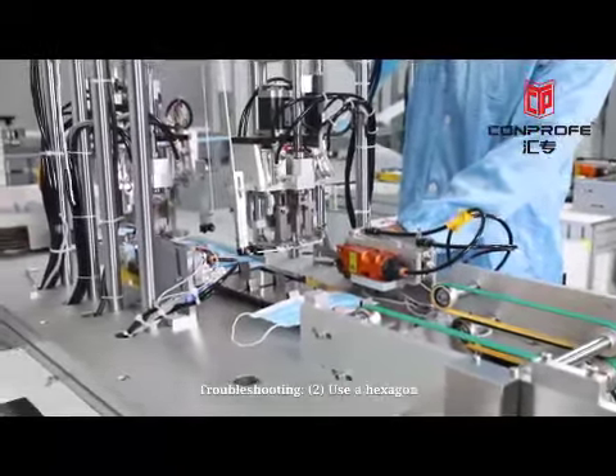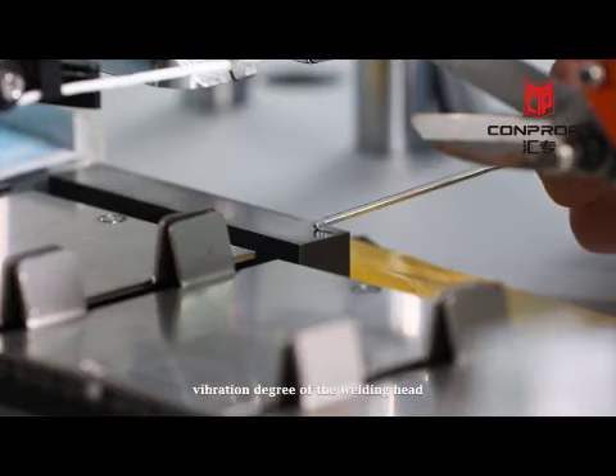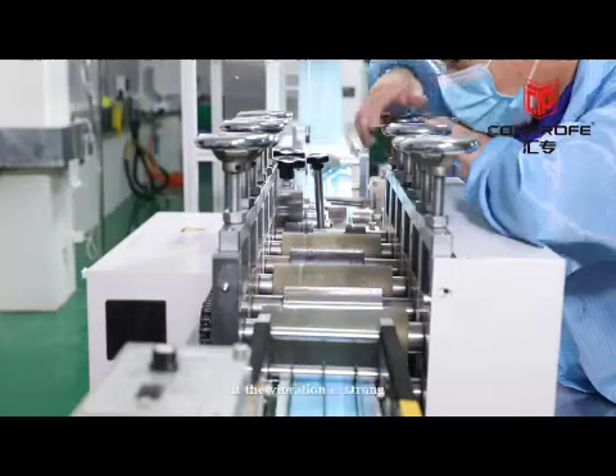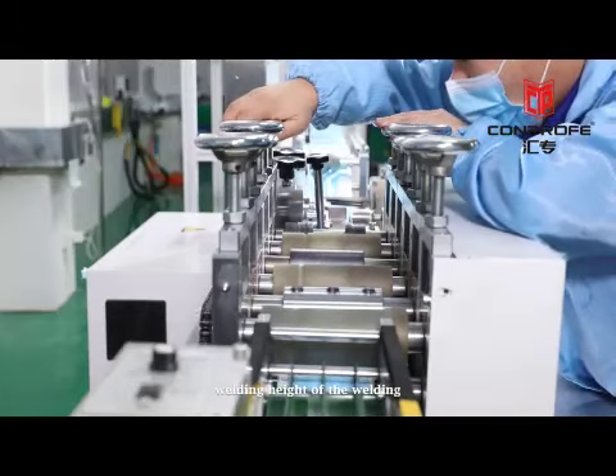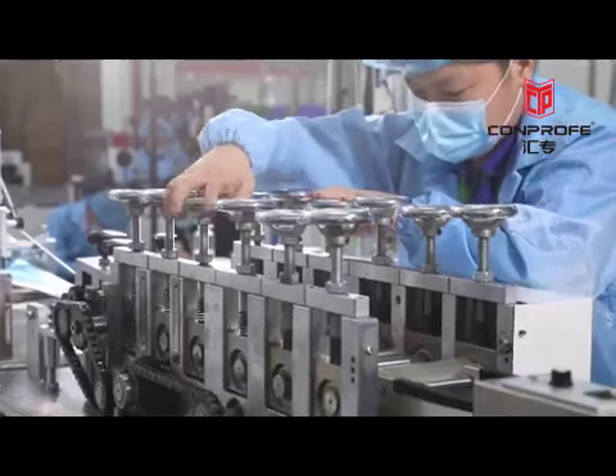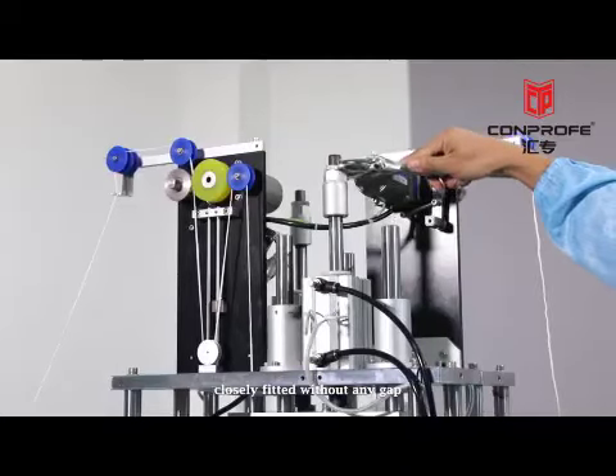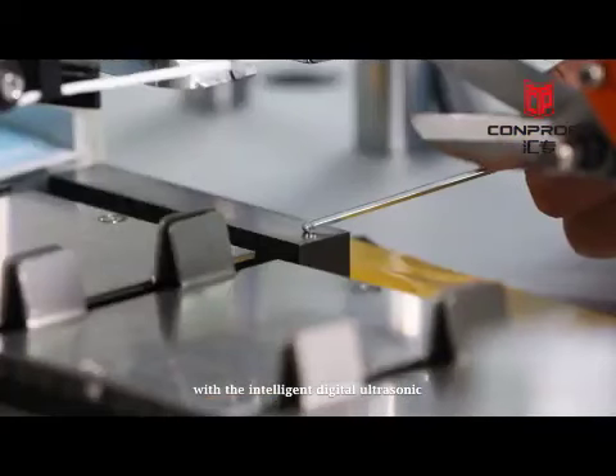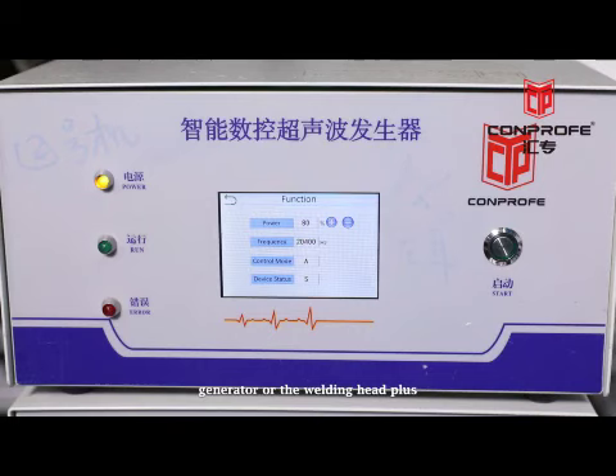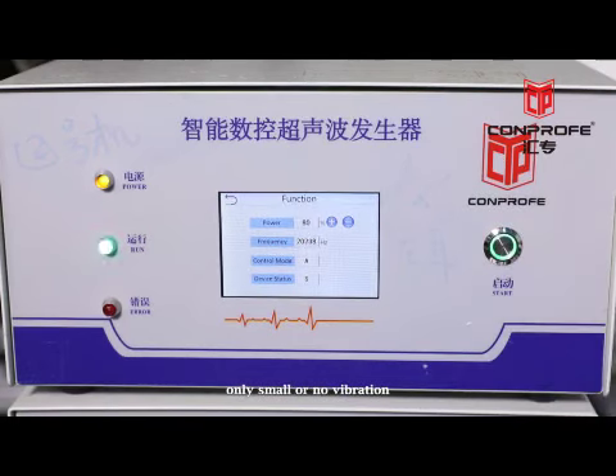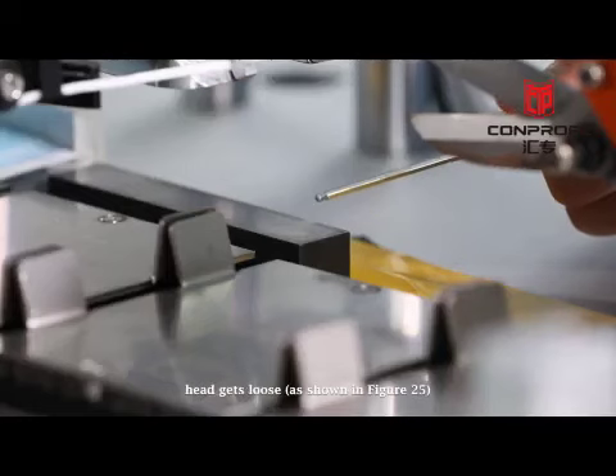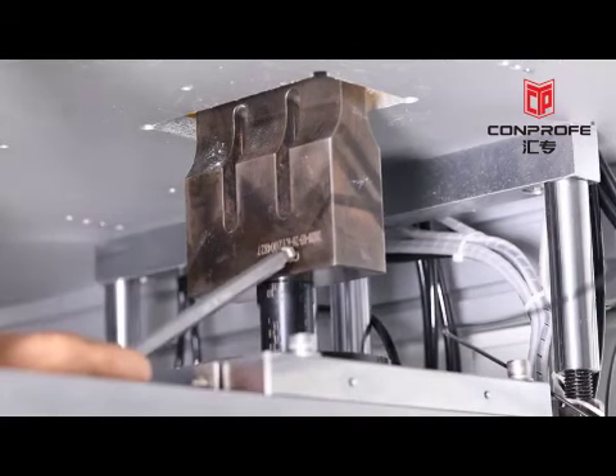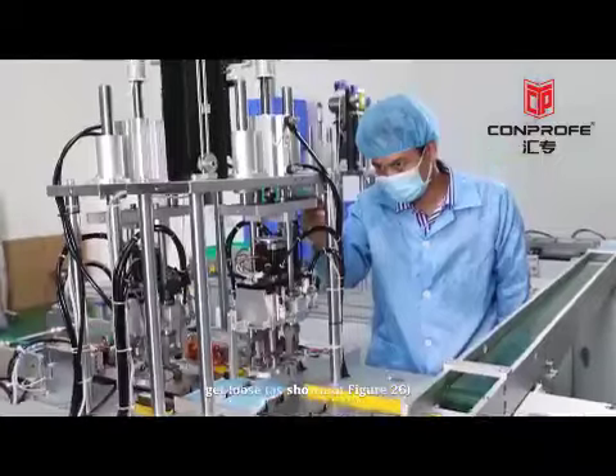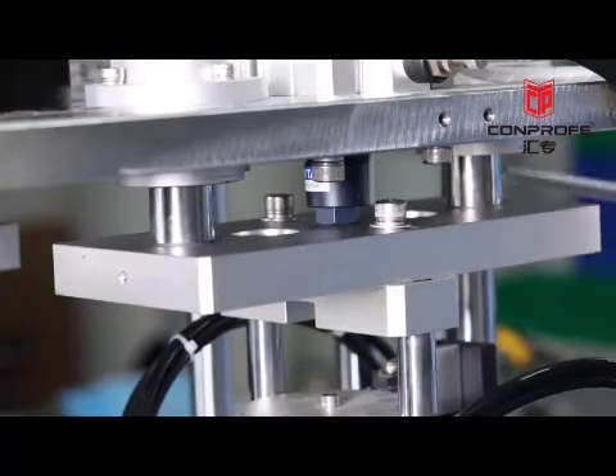Troubleshooting. 2. Use a hexagon wrench or a metal tool to test the vibration degree of the welding head and determine the vibration. If the vibration is strong, then determine whether the welding height of the welding head's contact surface is appropriate, and whether the welding head is closely fitted without any gap. Check whether there is a problem with the intelligent digital ultrasonic generator or the welding head plus the transducer if there is only small or no vibration. Interchange the intelligent digital ultrasonic generator for manual no-load test to check its vibration. Check whether the welding head gets loose, as shown in Figure 25, and whether the screws get loose, as shown in Figure 26, if there is only small or no vibration.